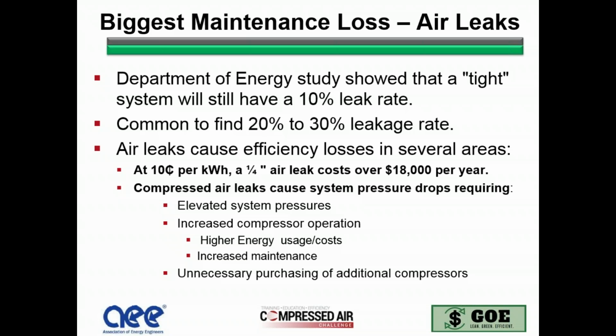If you look at what else it'll do, it also causes elevated system pressures for those unregulated leaks. It's going to cause you to increase the compressor operation, which means not only the higher energy costs we talked about, but increased maintenance. And then also the unnecessary purchase of additional equipment, because many times, rather than repair the leaks, when you start running out of air, what do we do? We buy another compressor. So that's an important part that needs to be taken into consideration.